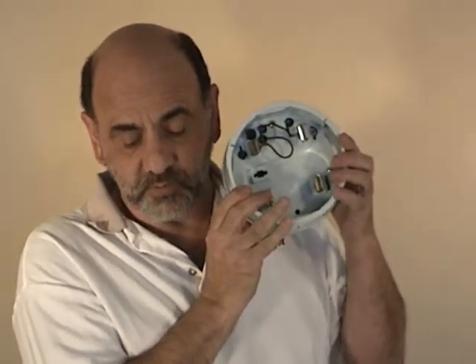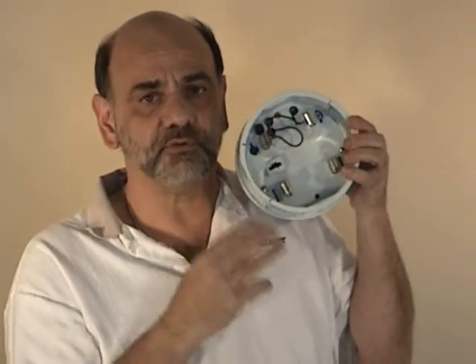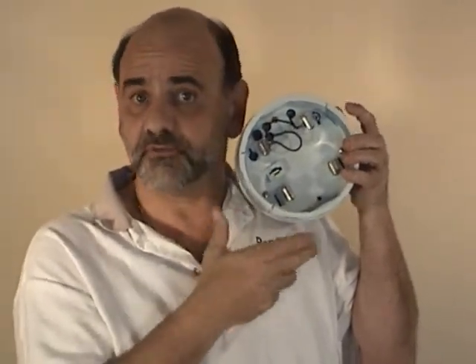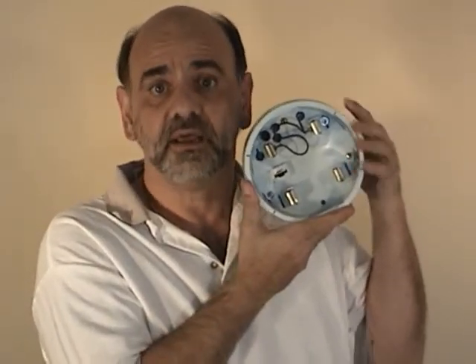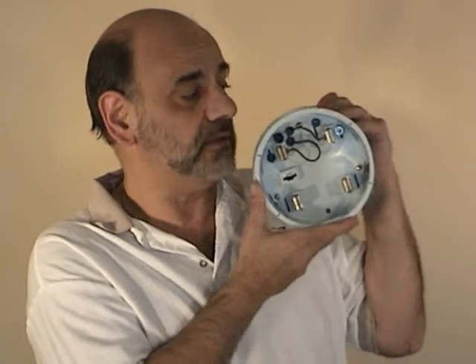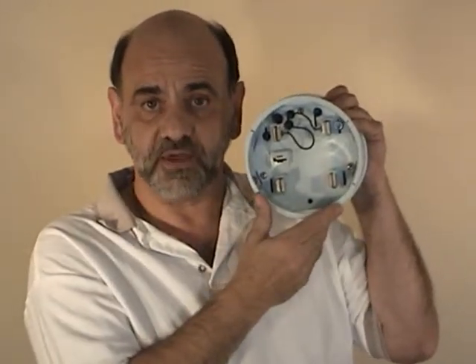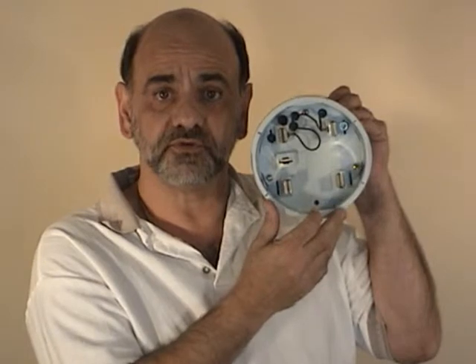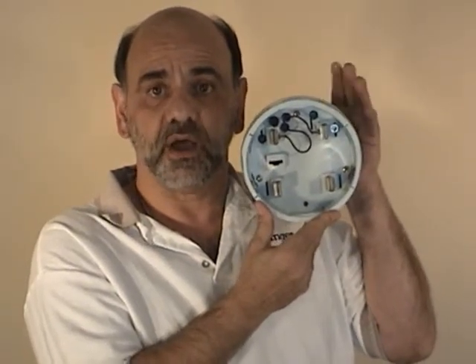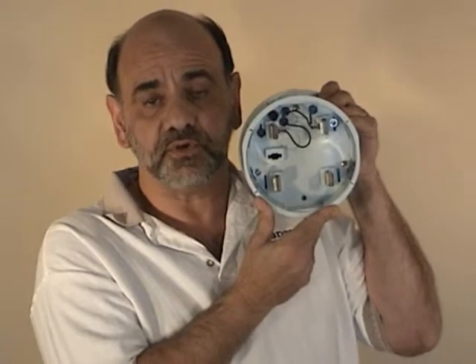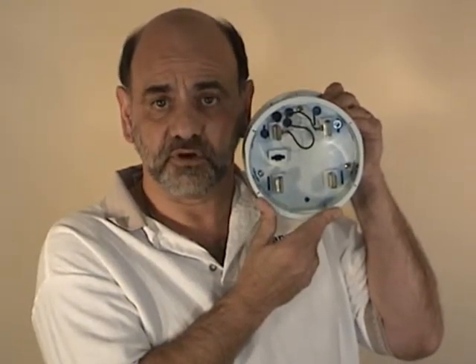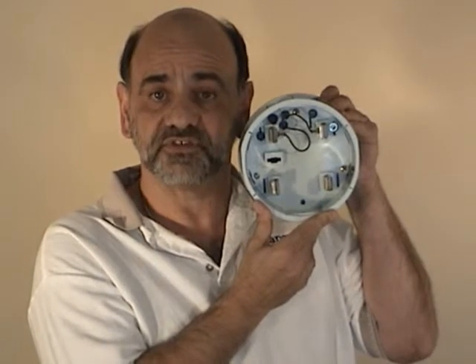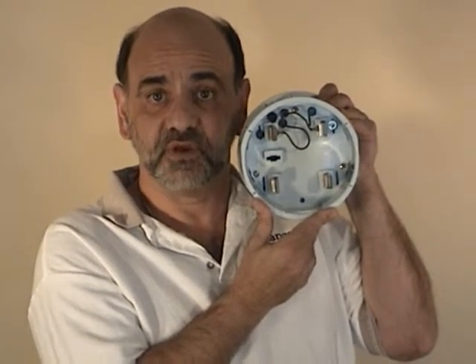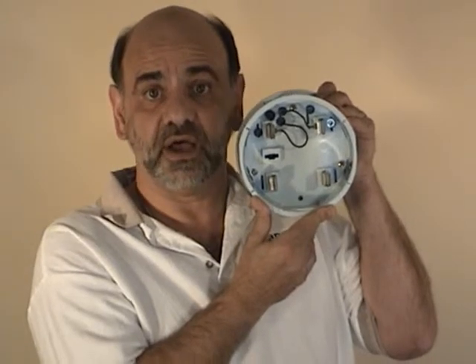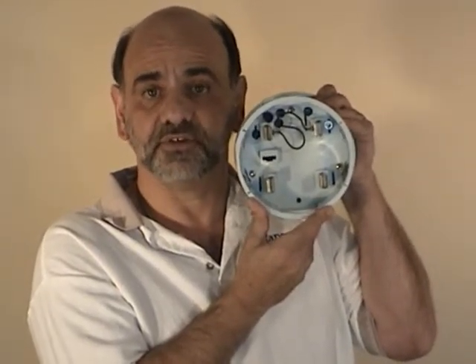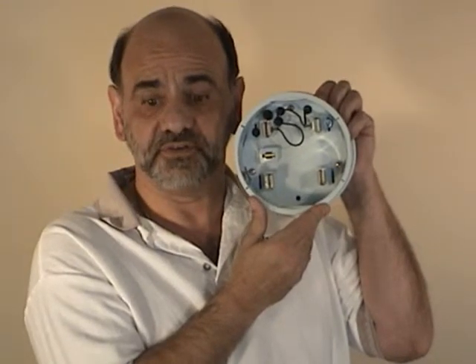The first setup records all three voltages. And remember, we do record L1 to L2, 0 to 300 volts. We're the only one in the industry that can do that with a meter socket logger. That 0 to 300 volts is a measured value and recorded. We do L1 to neutral, L2 to neutral, and the 0 to 200 amp L1 and L2 current legs. And we use a solid toroid style Rogowski coil technology to do that, which allows us to literally read down to 0 amps. So we are 0 to 300 volts on L1 to L2 and 0 to 200 amps on both of our legs of current.